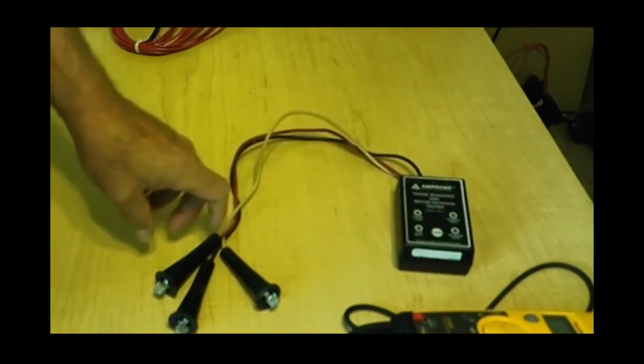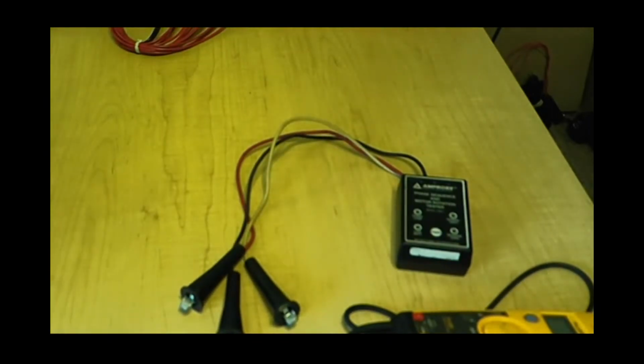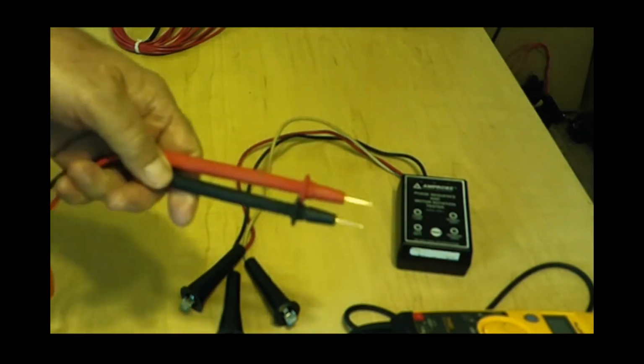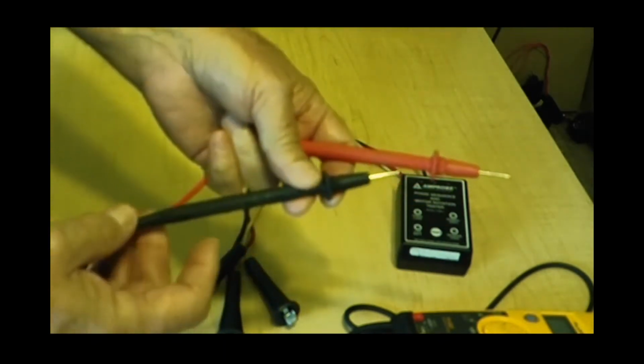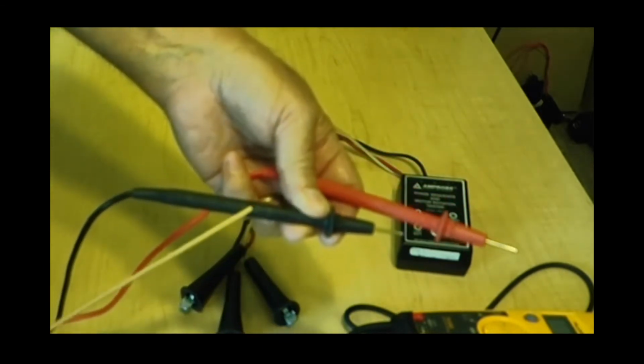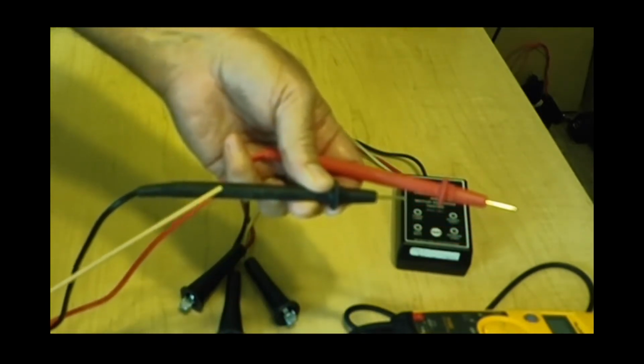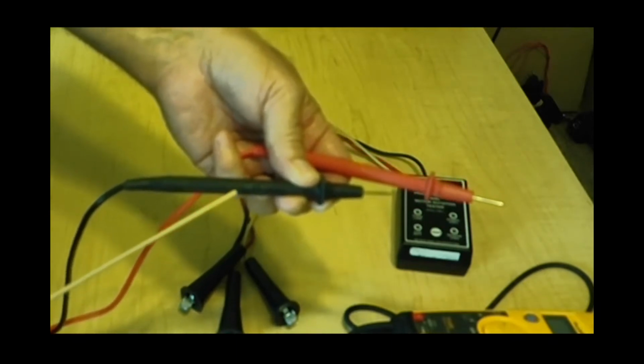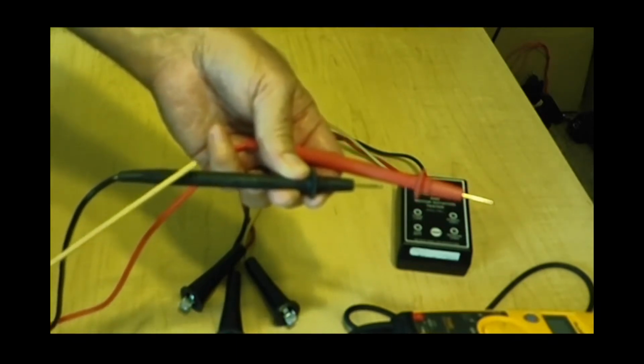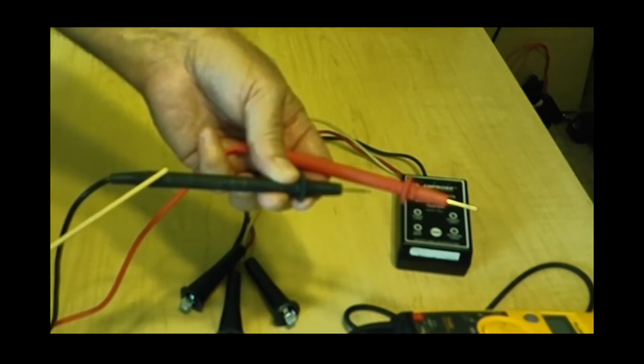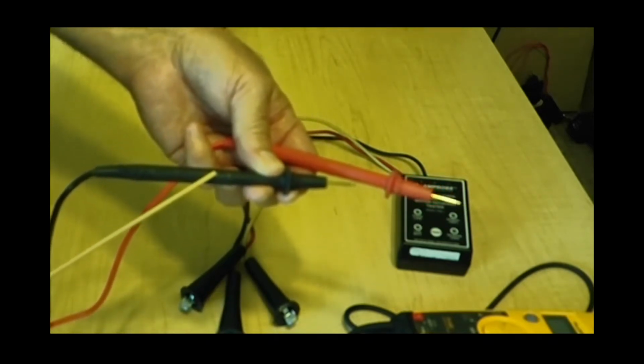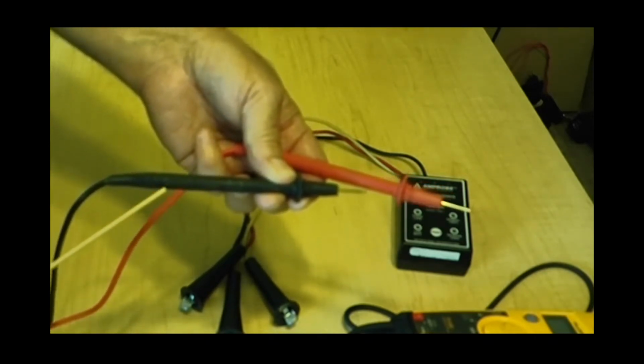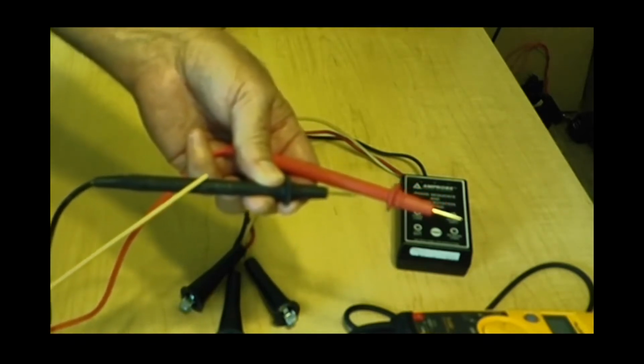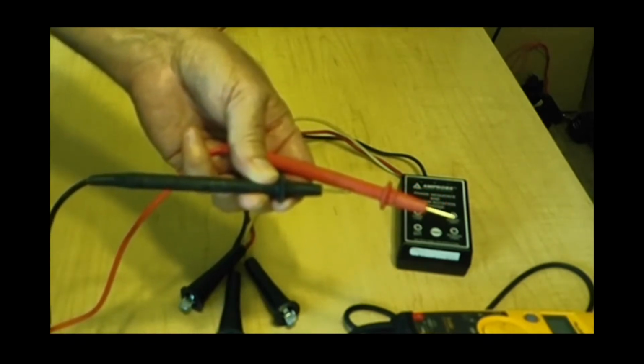Now, we start looking at all these different types of meters. I grab a pair of test leads. The test leads we use in a meter are going to have ratings on them. It's going to have a voltage rating and a category rating. Now, it's kind of important that we use a test lead that's rated for the voltage we're going to measure and the category we're going to be used in. So most of these will say 1000 volts Cat 3 or 1000 volts Cat 4.